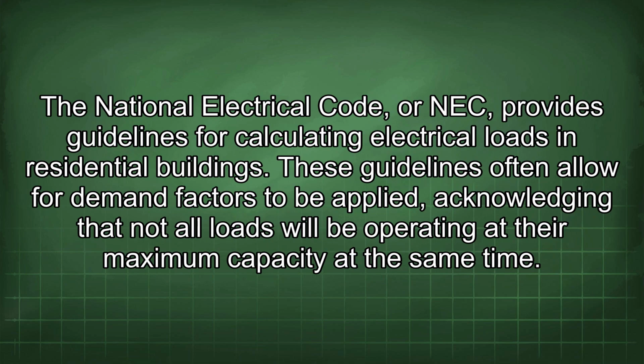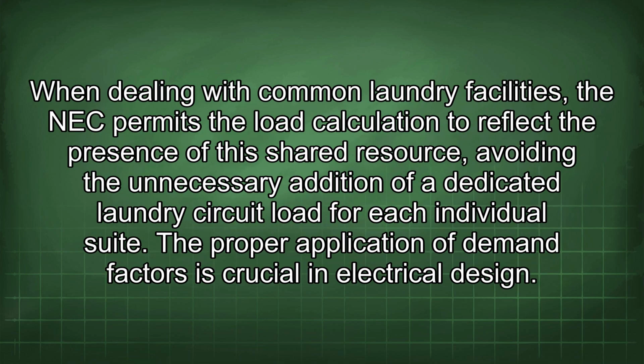The National Electrical Code, or NEC, provides guidelines for calculating electrical loads in residential buildings. These guidelines often allow for demand factors to be applied, acknowledging that not all loads will be operating at their maximum capacity at the same time. When dealing with common laundry facilities, the NEC permits the load calculation to reflect the presence of this shared resource, avoiding the unnecessary addition of a dedicated laundry circuit load for each individual suite.